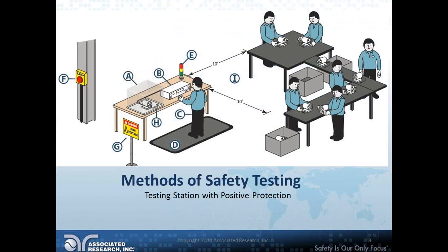I there shows other operators working at other stations. They are not qualified to work with that test equipment, so we have the 10-foot rule there. Now, the 10-foot rule comes into place with exposed conductors. Technically those guys could be closer than 10 feet because you're using an enclosure door there, so it's not an exposed conductor. If you have a DUT enclosure door over what you're testing, you can have other operations going on closer than 10 feet. You won't get in trouble for that because the conductor isn't exposed. I wanted to make that clear since it's not obvious from the picture.